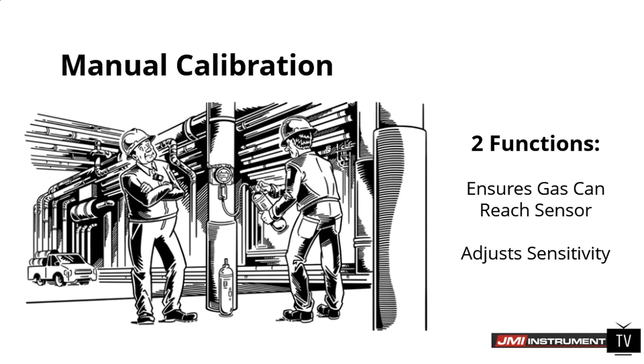So manual calibration actually serves two functions. One, we want to make sure that the gas from the bottle and the tubing can reach the sensor. That's maybe a less thought of one. And then, of course, we want to adjust for the sensitivity. The sensitivity we're adjusting for is either the electrolyte loss from sensing gas itself, or temperature and humidity changes within its own environment. That's the purpose of why we do a calibration.